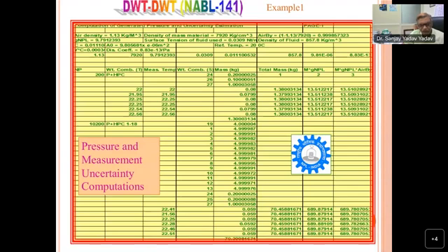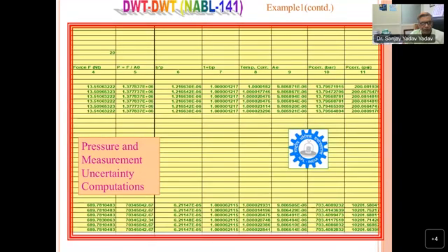For example, these are the weights on the deadweight tester: 24, 26, 27. 27 is the piston and hanger mass, and 24 and 26 are individually placed. Here are the corresponding mass values, and then you make the summation. With respect to repeated measurement of temperature, this small fraction is adjusted on the deadweight tester in grams or milligrams, and then you make the total mass. The total mass for the individual 6 readings is here. Then you multiply by the G value, M into local G value, and then multiply by the air buoyancy correction. Then gamma C you can add. So your numerator is now determined, which is called the force on the piston.